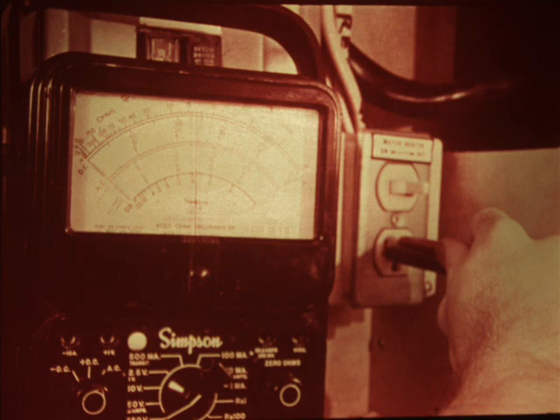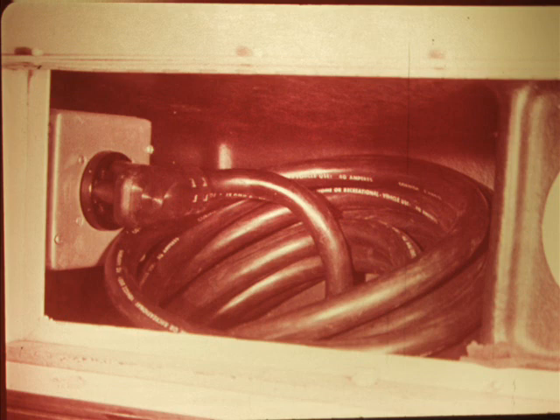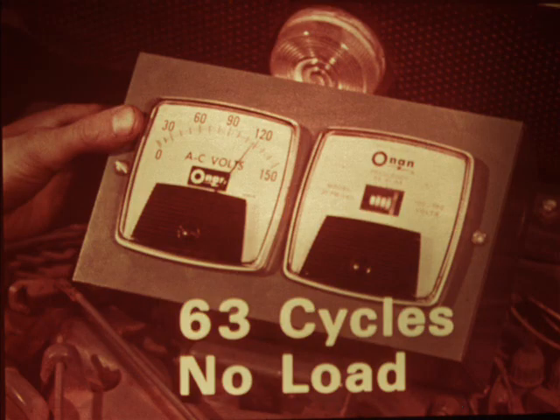Or if the power source is questionable, test the converter output with all other 120-volt equipment turned off. If the problem seems to be no charging when the converter is being fed from the motor generator, the generator output may not be right. To test the motor generator output, first disconnect all 120-volt sources.